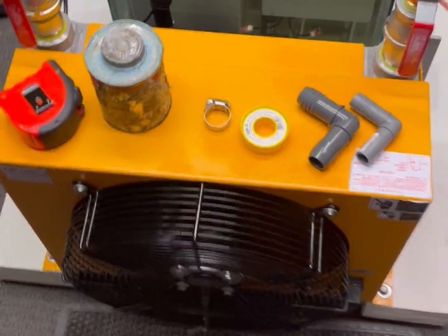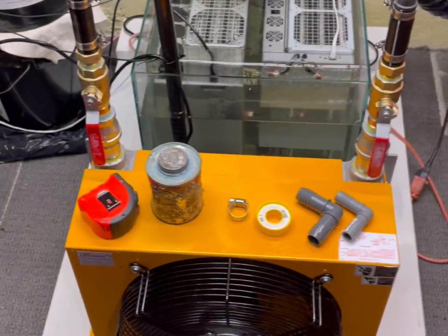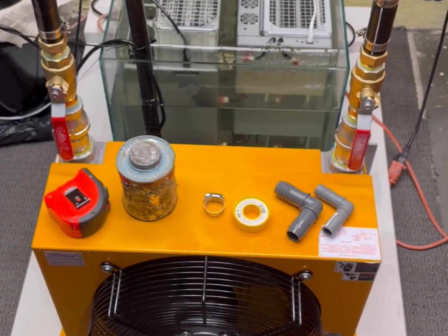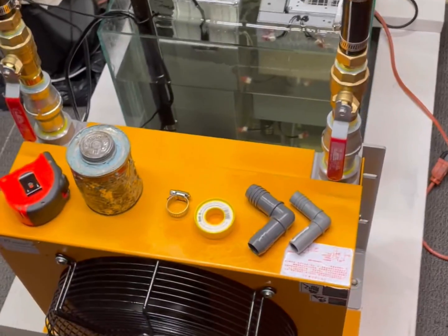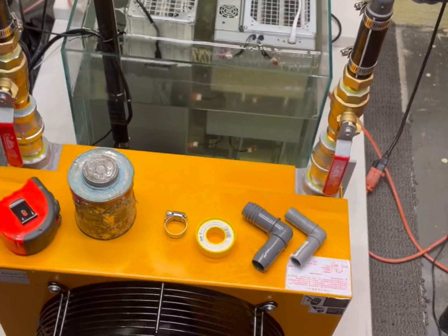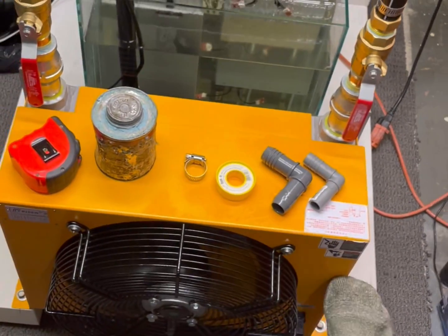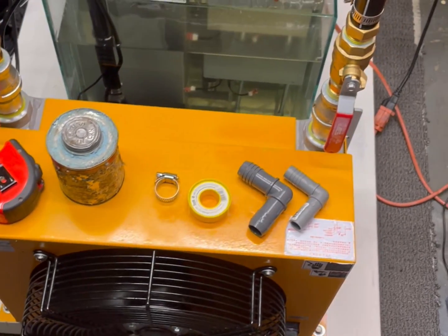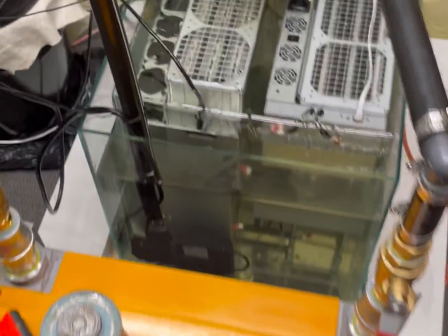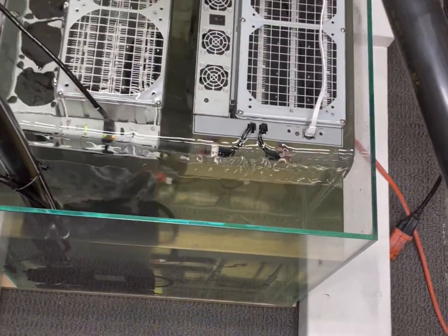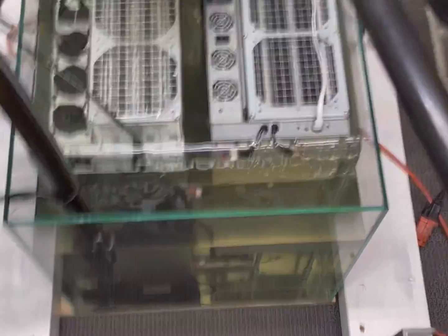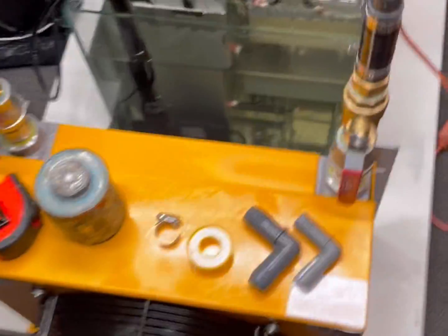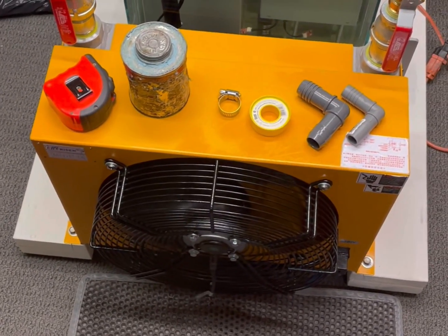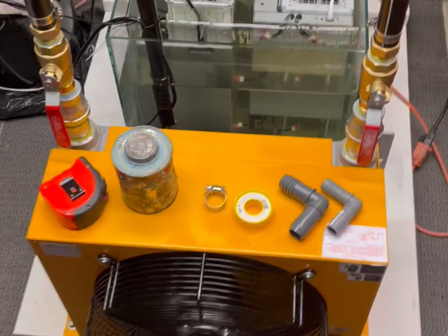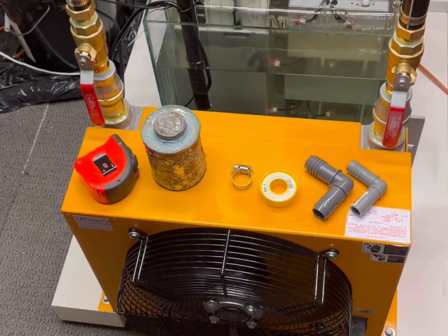So for this specific rad, there's not much information out there on how to size it for the wattage you're putting out, and if you look at the numbers online, they don't actually make sense. This one had a rating of about 77,000 BTUs cooling capacity, and combining both miners, on paper it appeared they'd need the equivalent of about 22,000 BTUs. I thought I'd be good to go for both, but it doesn't actually translate that way - for whatever reason you're only probably going to get about 15% of the rated cooling capacity.